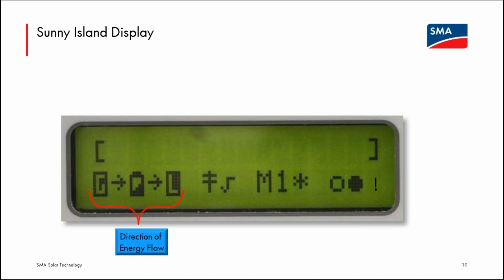The lower line of the display shows power flows. We see in this scenario, power is coming from the G, which could be the grid or the generator. Right now you see the utility pole right next to that. The grid status is good, so the G would be grid power coming past the Sunny Islands, perhaps recharging the batteries, and providing power to the protected loads panel.